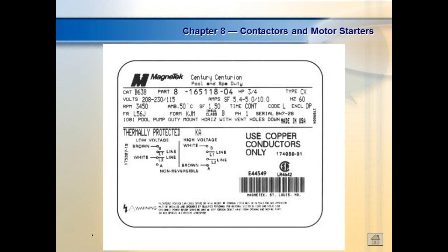This is a 3/4 horsepower motor, guys. It's going to deliver 3/4 horsepower. If you do it at a lower voltage, it's still going to try to deliver 3/4 horsepower, which just means it's going to pull more current, right? So that's why you can burn a motor up if you run it on a voltage that's too low. Because if you got a 10 horsepower motor, by George, that motor is going to try to produce 10 horsepower, 746 watts per horsepower. If you put that sucker on a too low voltage, you could burn the motor up.